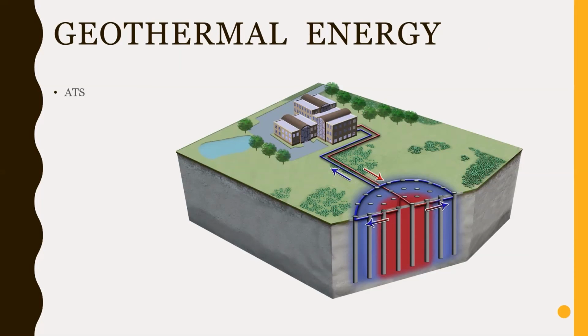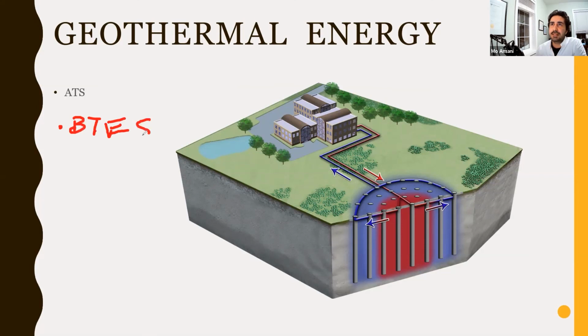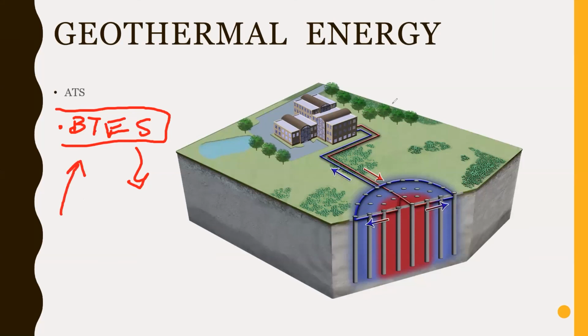Usually for homes I use 5 tons. In my home I have 2.5 tons, usually 3 to 5 tons, and my home is 4,000 square feet. So for a BTES system, if I wanted to design it, what's the feasible minimum kilowatt to convince a client to go with this? I'll throw out numbers from experience: a 500-foot borehole is good for 3 tons, you'll have no issue.